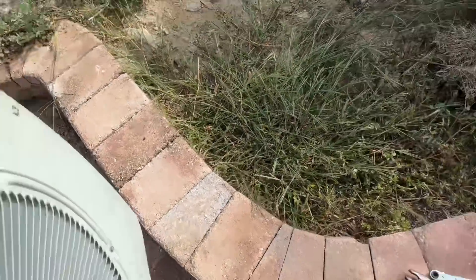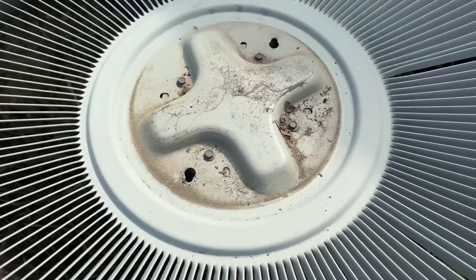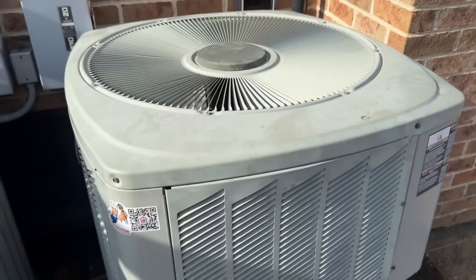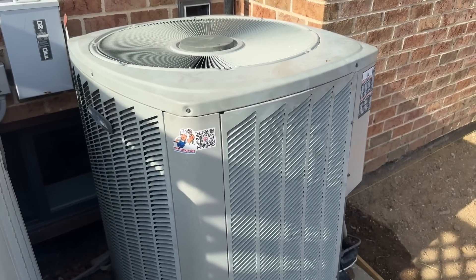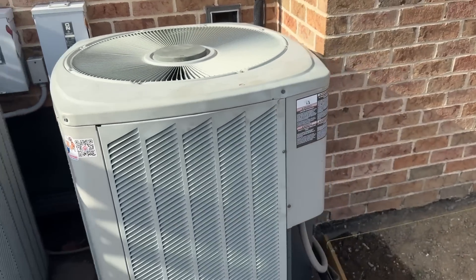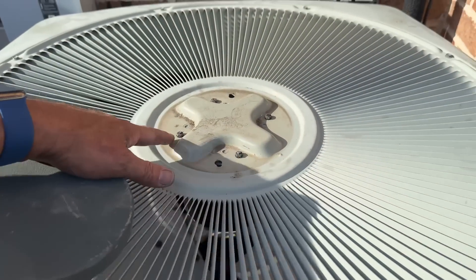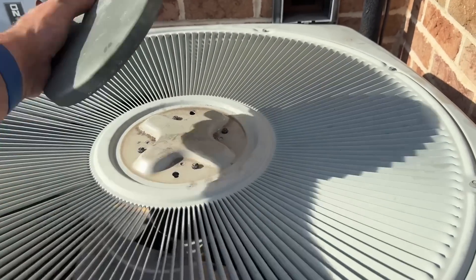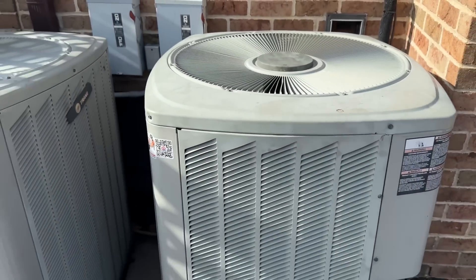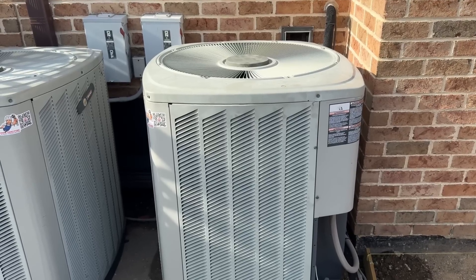Let's do this in the dirt — I don't want to damage the paving stones. Alright, let's lock it in. You hear that compressor running? Wow. So I got a new 1/8 horsepower, 825 RPM, 208/240 condenser fan motor in there. Used my grinder, cut back those bolt heads. Nice and tight. We're good — we're discharging hot air from inside the house and she lives another day.